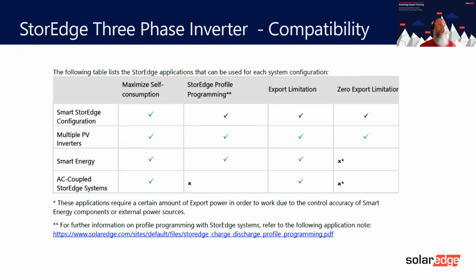So just a couple of notes on here. With smart energy, zero export is not supported because smart energy needs about 50 watts so it can detect that there's actually an export, and then it will come on. So you can actually trick the system by setting it to export at 50 watts. 50 watts is not enough to cause a problem, because as soon as it reads 50 watts, it's going to go into the smart energy anyway.